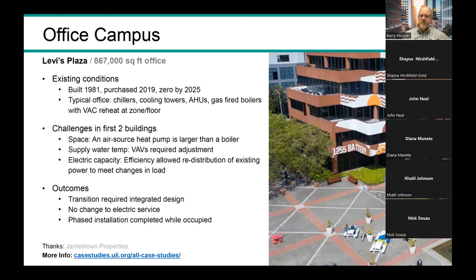This means there are some initial challenges their team had to evaluate. An air source heat pump is generally larger than a boiler, but generally smaller than the combination of a boiler and a chiller — though the boiler and chiller may not occupy the same space. So there can be a real space constraint for the engineers to figure out how to make the new system work, how to redesign within the existing building.